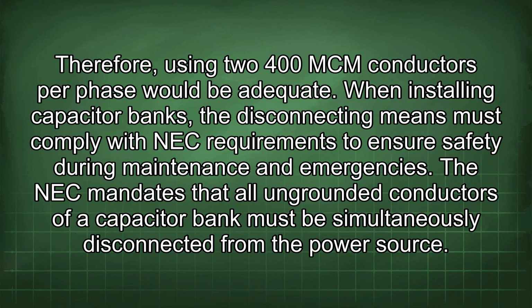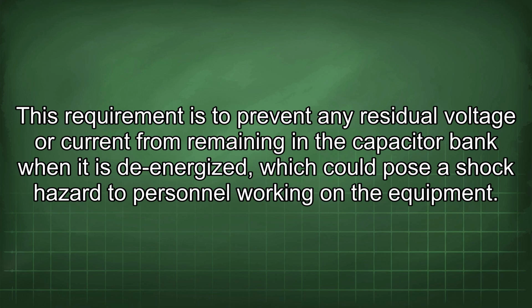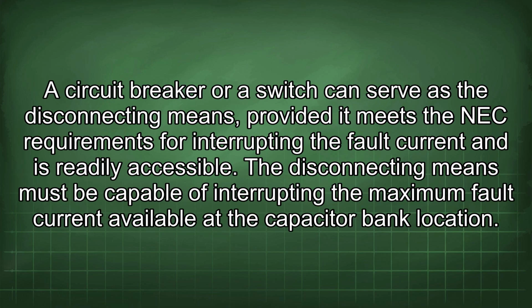When installing capacitor banks, the disconnecting means must comply with NEC requirements to ensure safety during maintenance and emergencies. The NEC mandates that all ungrounded conductors of a capacitor bank must be simultaneously disconnected from the power source. This requirement is to prevent any residual voltage or current from remaining in the capacitor bank when it is de-energized, which could pose a shock hazard to personnel working on the equipment. A circuit breaker or a switch can serve as the disconnecting means provided it meets the NEC requirements for interrupting the fault current and is readily accessible.